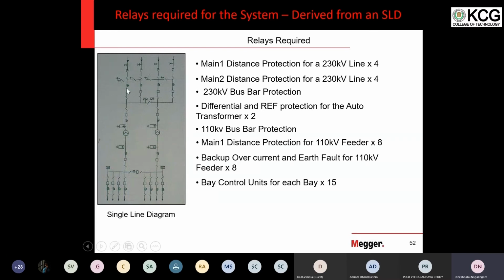A bay is the breaker and the associated equipment together: isolator, earth switch, everything. This we call bay 1. Any number you can give. Just for example, I'm telling bay 1, bay 2, bay 3, bay 4. Like that, you can keep on giving bay numbers: 5, 6, 7, 8, 9, 10, 11, 12, 13, 14, 15. So how many breakers are there? 15 breakers, so 15 bays. I did not count this because this is not a bay. There is no breaker. So even if there is a fault in that system, you cannot trip that particular area because an isolator cannot trip for a fault. Therefore, there is no meaning in calling it a bay and giving it separate protection and control.